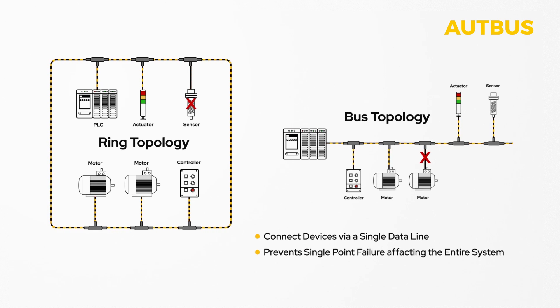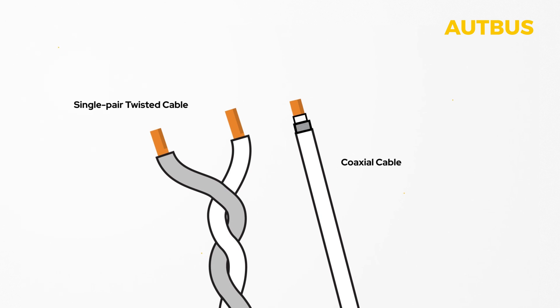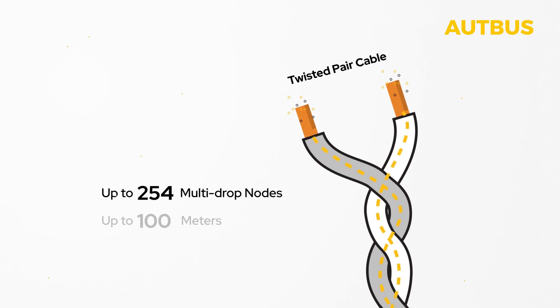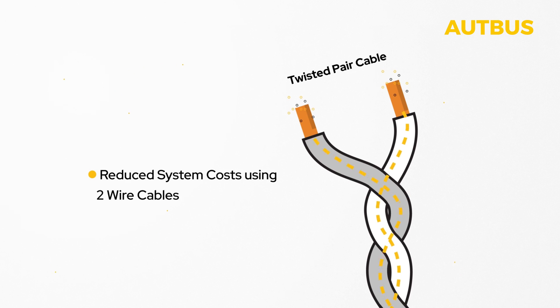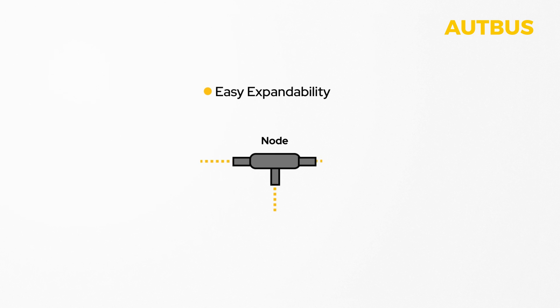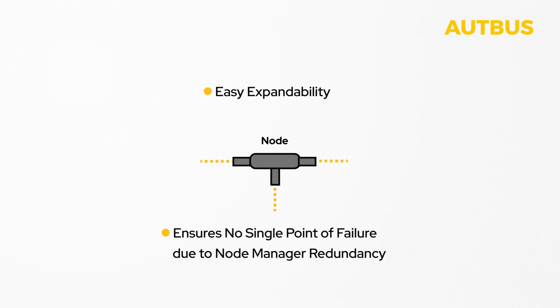AUTBUS supports both balanced and unbalanced cables. Using a qualified twisted pair or coaxial cable, it can reach up to 254 multi-drop data network nodes over distances of up to 100 meters, maintaining a transmission speed of 100 megabits per second. System cost is reduced through the use of cost-effective two-wire cables and a reduced number of data cables due to multi-drop connections and simplified installation. It also boasts easy expandability and ensures no single point of failure due to node manager redundancy.